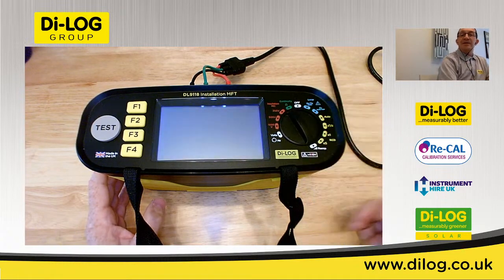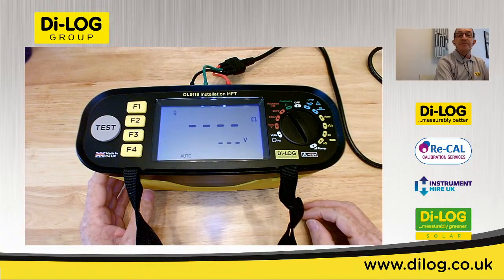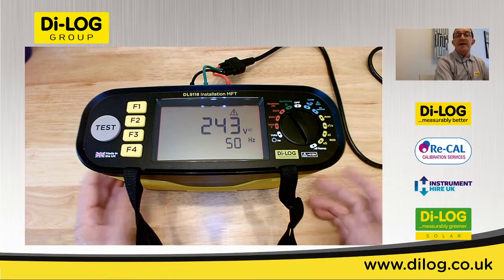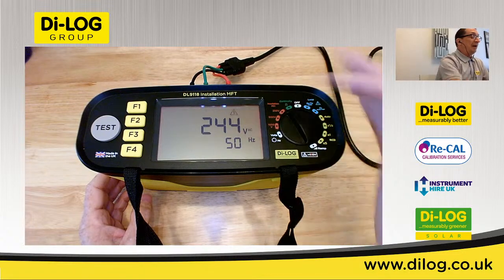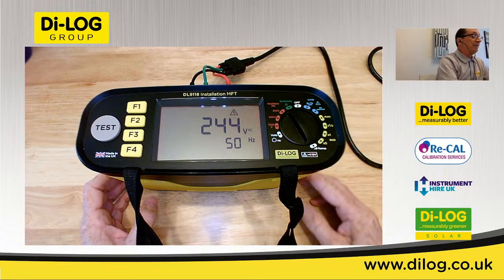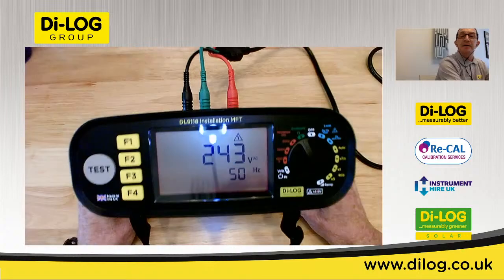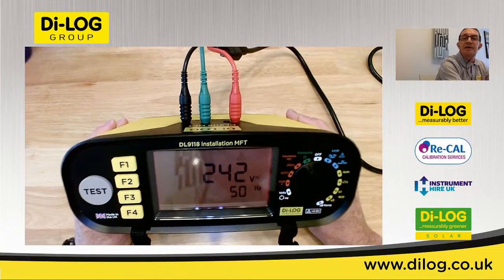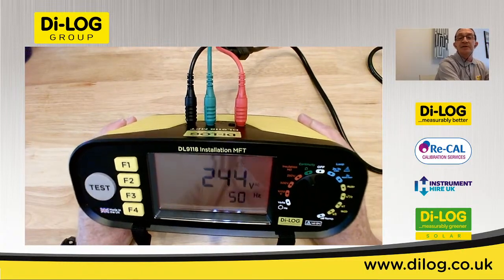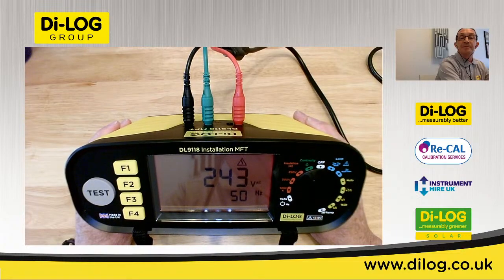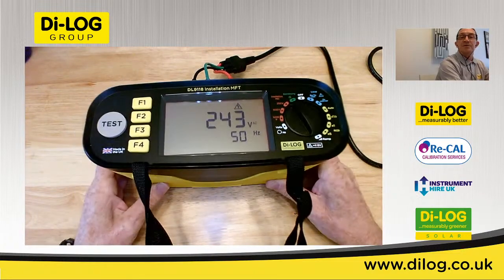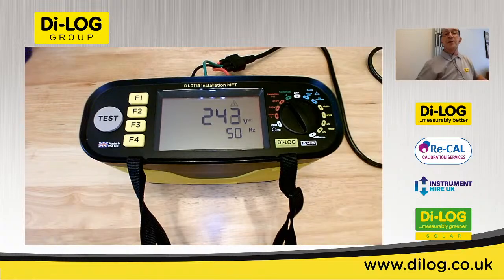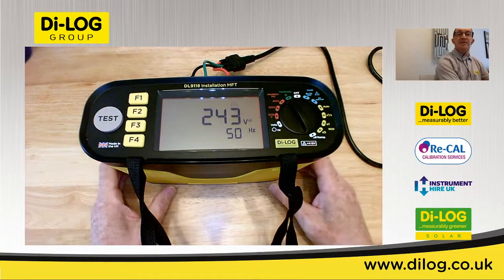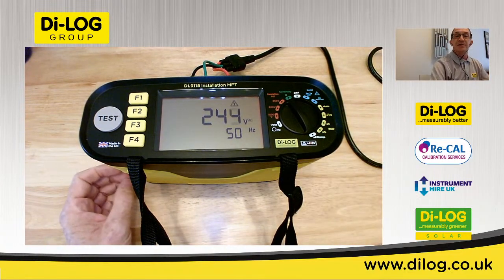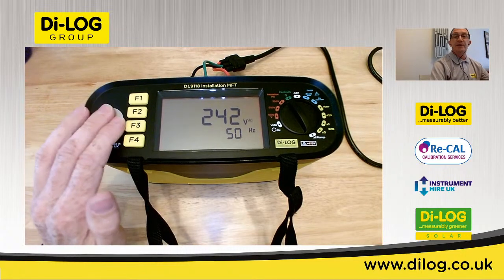So if I put voltage on continuity, I get two indications. I get an audible warning and a visual indication too. And if I position that correctly, you may be able to see that the display has changed bright red. So if you do happen to make an error and put voltage where you shouldn't do, this unit is giving you plenty of warning that you need to make some changes. And the test button is also inhibited.